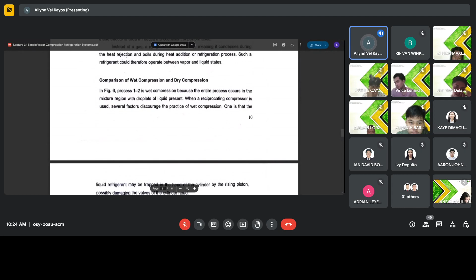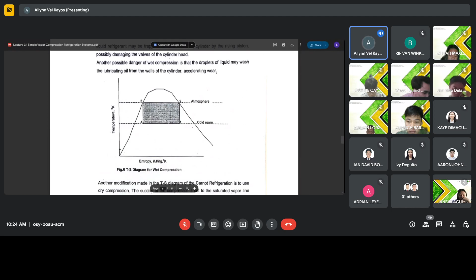When a reciprocating compressor is used, several factors discourage the practice of wet compression. First, the liquid refrigerant may be trapped in the head of the cylinder by the rising piston, possibly damaging the valves of the cylinder head. Another possible danger of wet compression is that the droplets of liquid may wash the lubricating oil from the walls of the cylinder, which accelerates wear. So nagbigay sila ng two possible dangers of using wet compression, mostly nakaka-damage sa compressor.